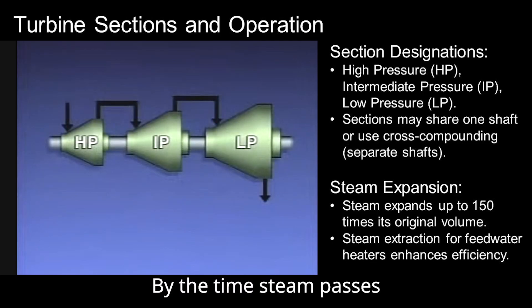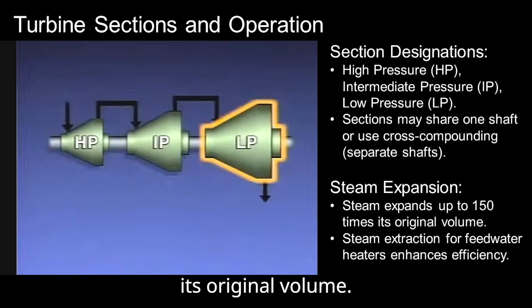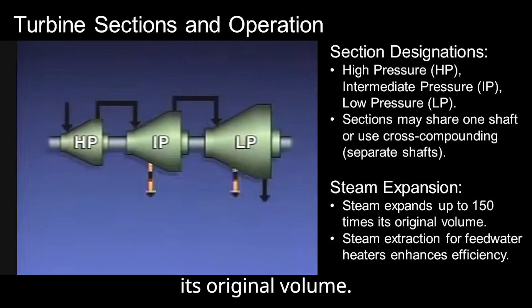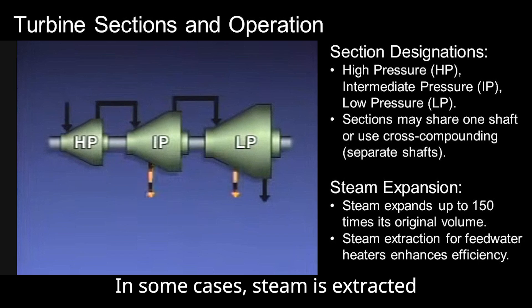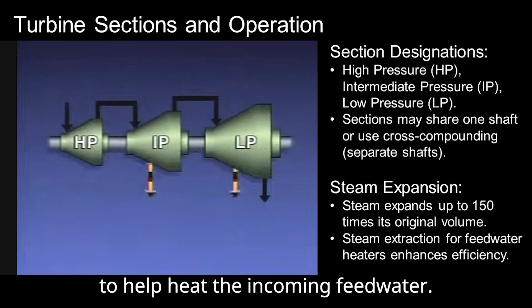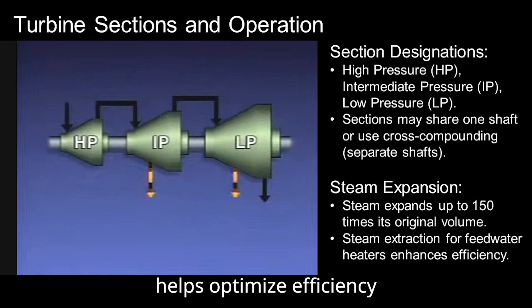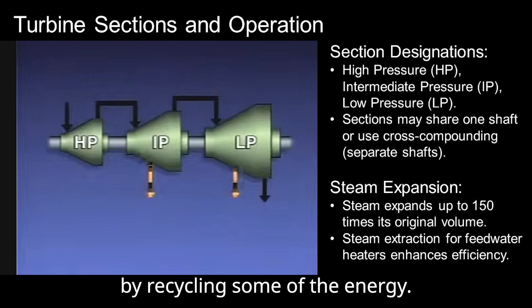By the time steam passes through all the stages, it can expand up to 150 times its original volume. In some cases, steam is extracted and sent to a feed water heater to help heat the incoming feed water. This extraction process helps optimize efficiency by recycling some of the energy.